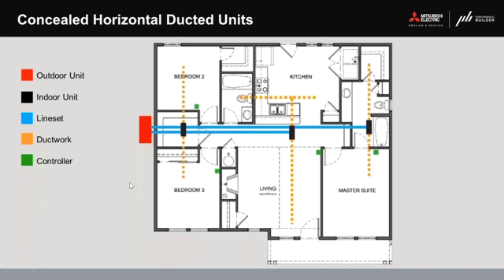But like I mentioned before, they're really useful if you've got, say, a vented attic and you want to get all of your mechanical systems into conditioned space, because that is one thing I didn't call out earlier in the load calculation portion: getting your mechanical systems into conditioned space can easily take a ton or 2 tons off of a cooling load, depending on where your project is located. So just getting it out of the attic and inside your thermal and air control layers can have a huge impact on that load.